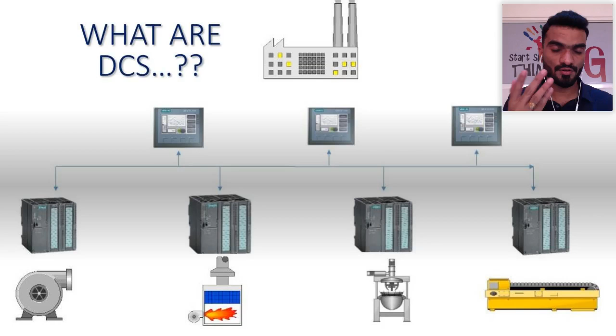For each application or segment we have dedicated function blocks focused on analog signals or levels, for certain areas. All these function blocks are ready-made in the DCS. You just take the function block, activate it, and communicate with that particular PLC. Then the entire data of that area or machine can be taken into the DCS, and you can control the entire plant. It's like a master control system where you can have redundancy, so if something goes wrong, another system can act immediately.